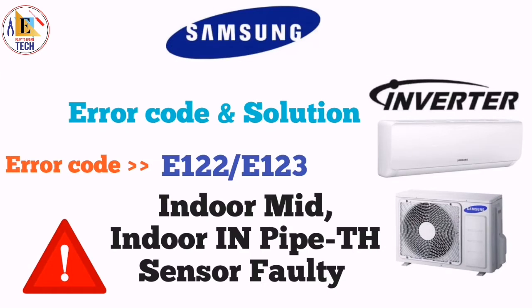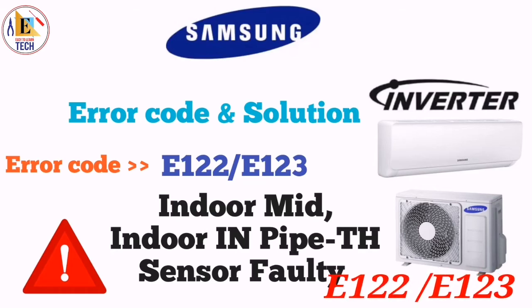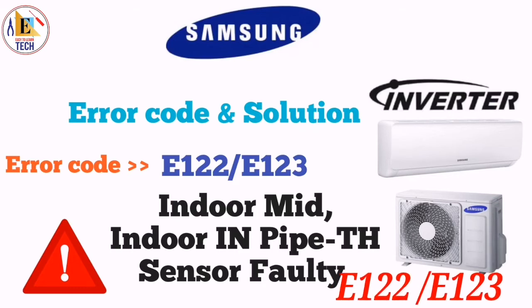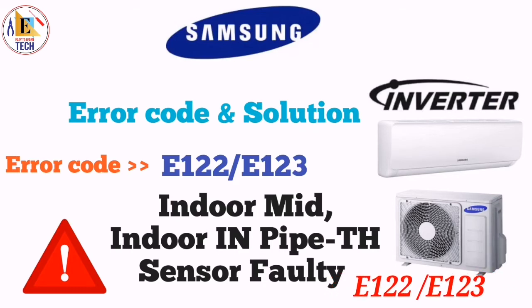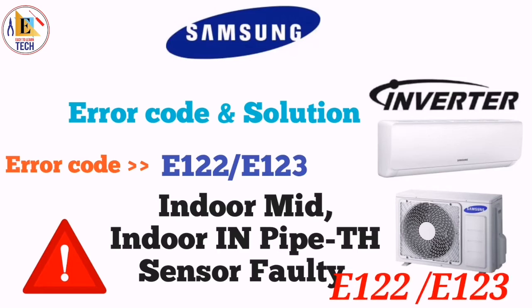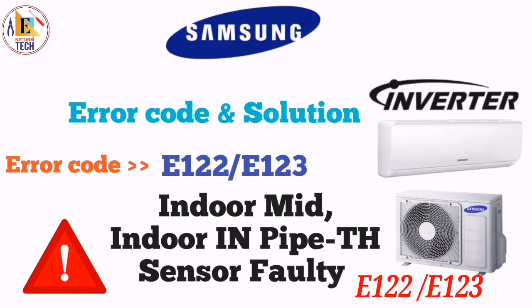When you see error E122 or E123, it means it's an indoor in-pipe TH sensor error. Or if you have 3 LED light, when LED 1 and LED 2 are blinking and LED 3 is off, at that time also it shows the same error, indoor in-pipe TH sensor error. For this, first of all, you have to detach the assembled sensor from the PCB sensor connector and measure the sensor resistance with an ohm meter or tester.